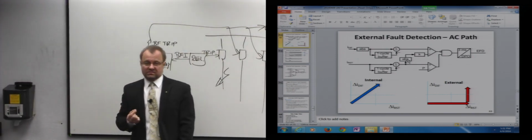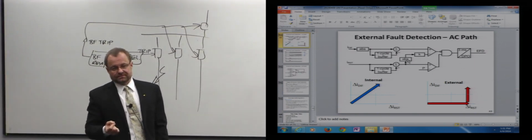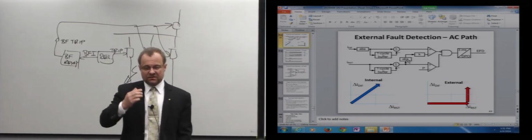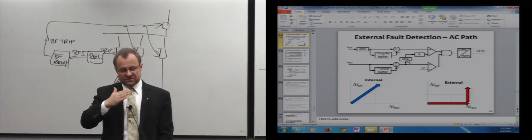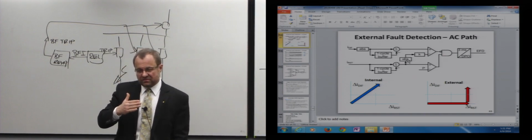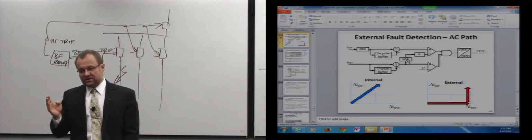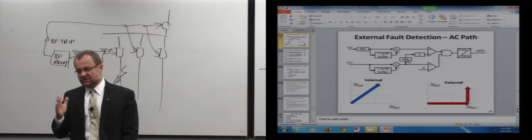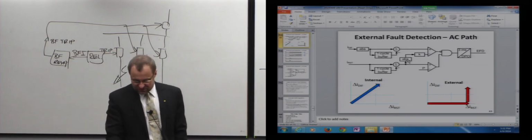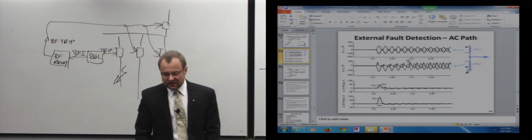Get ready because CTs could saturate. So knowing that, I could adjust my countermeasures, I could become prepared for it, and I am not going to sacrifice sensitivity or speed on internal faults. Because on internal faults, this logic will never engage. This is how it works.